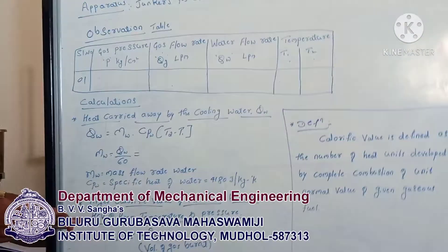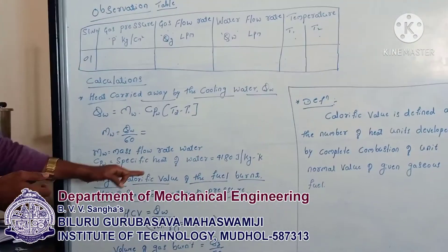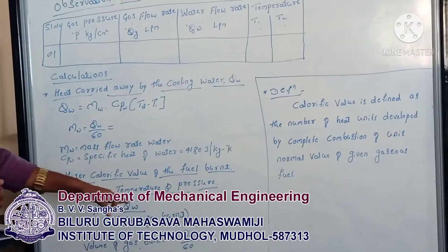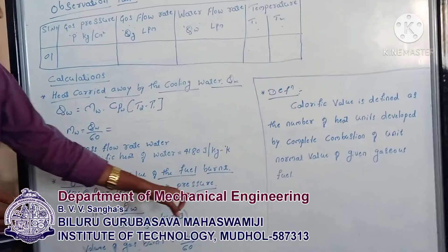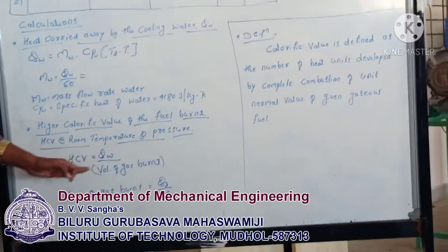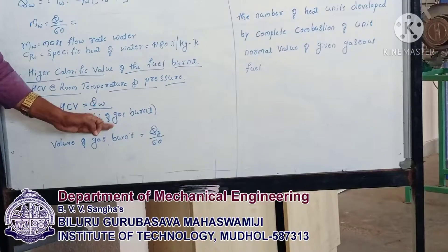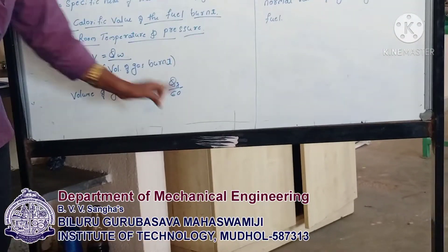Another formula is HCV — the Higher Calorific Value of the fuel burned at room temperature and pressure. HCV is equal to Qw divided by the volume of gas burned. The volume of gas burned is calculated as gas flow rate divided by 60.